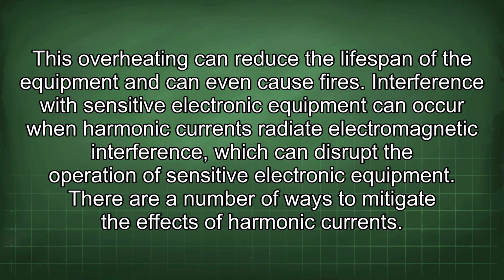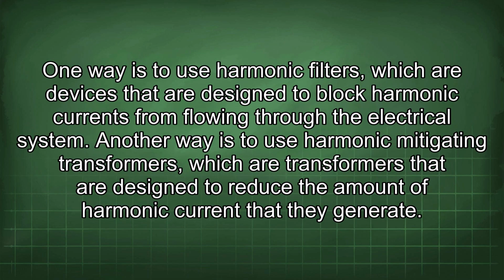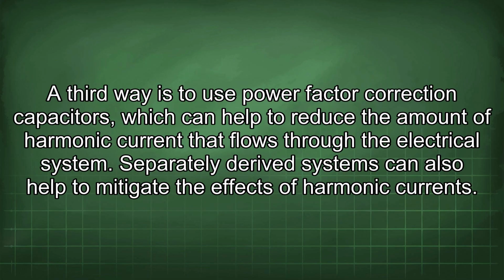Interference with sensitive electronic equipment can occur when harmonic currents radiate electromagnetic interference, which can disrupt the operation of sensitive electronic equipment. There are a number of ways to mitigate the effects of harmonic currents. One way is to use harmonic filters, which are devices that are designed to block harmonic currents from flowing through the electrical system. Another way is to use harmonic mitigating transformers, which are transformers that are designed to reduce the amount of harmonic current that they generate. A third way is to use power factor correction capacitors, which can help to reduce the amount of harmonic current that flows through the electrical system.